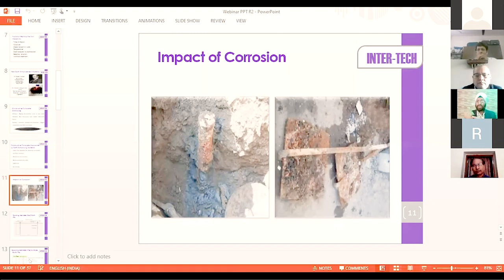When we add salt into the earth pit, we are adding moisture. When we add chemical into the earth pit, it means we are adding moisture, because chemical or bentonite is nothing but moisture-absorbing clay, which absorbs moisture that remains for some time. After some time it is not there, and that leads to corrosion. The presence of moisture leads to corrosion, and you can see on screen what happens when an earth pit gets corroded - how can you expect this earth pit to save lives when it is not even connected at all?